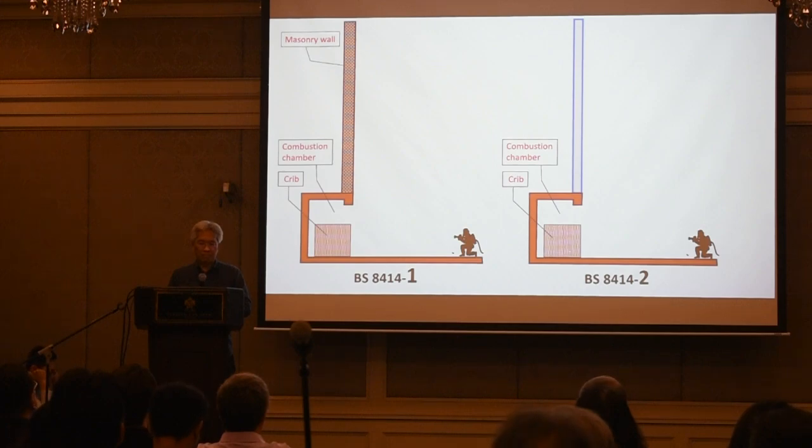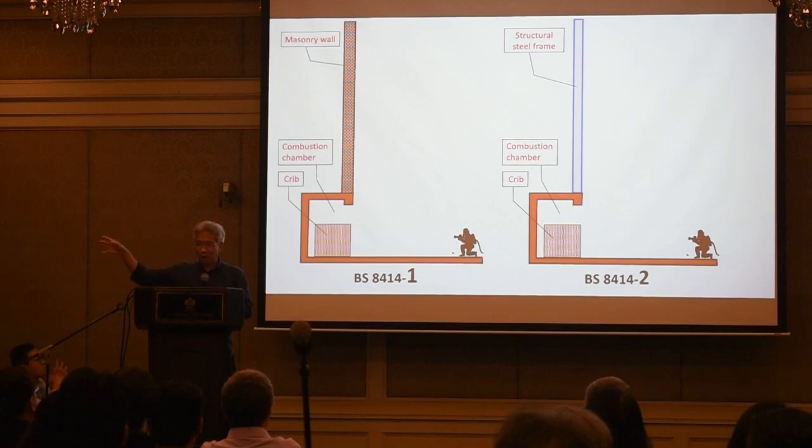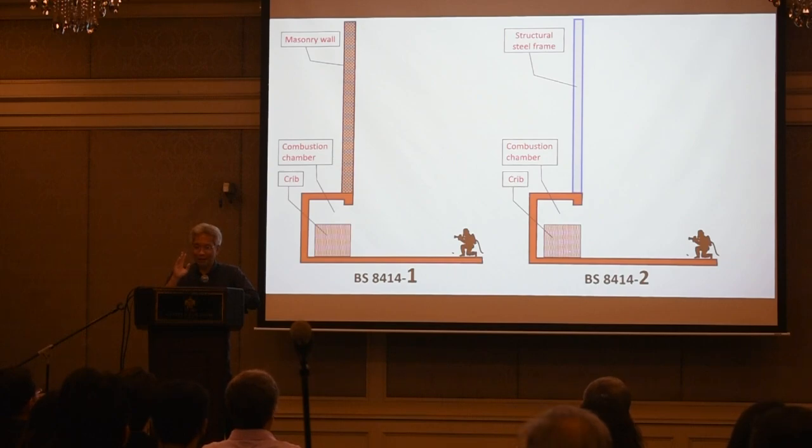And everything that you assemble, everything that you bring to be assembled onto this test rig will be part of your system. So if you have no intention of having that element on your wall, please don't put it in the sample. Okay, because this is called a homologation test. In other words, when you pass this one, you have to build that wall that you are going to build with all the same components that you put onto this test rig. If you have a variation on that component, they'll say, oh sorry, you're not building it in accordance to what was approved. So you have to be very, very careful.